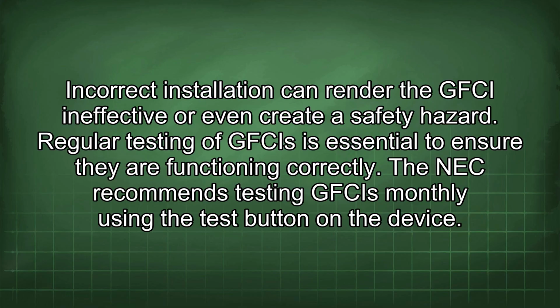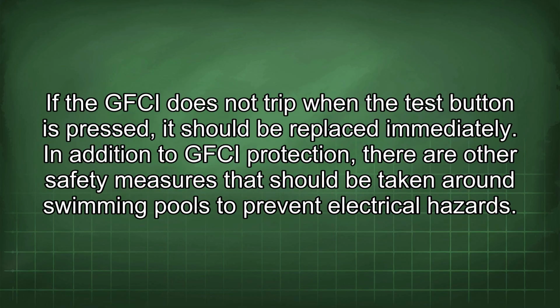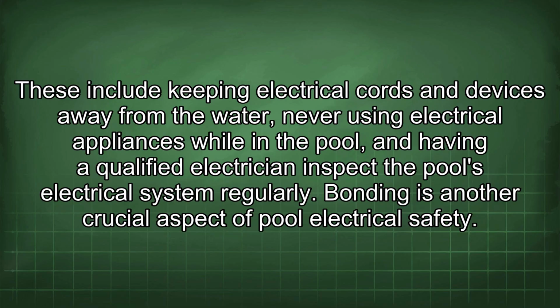Regular testing of GFCIs is essential to ensure they are functioning correctly. The NEC recommends testing GFCIs monthly using the test button on the device. If the GFCI does not trip when the test button is pressed, it should be replaced immediately. In addition to GFCI protection, there are other safety measures that should be taken around swimming pools to prevent electrical hazards. These include keeping electrical cords and devices away from the water, never using electrical appliances while in a pool, and having a qualified electrician inspect the pool's electrical system regularly.